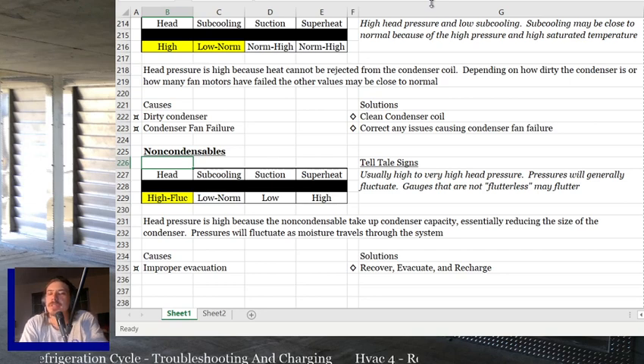But generally you're going to see head pressure start at 250, climb up to 300, 320, 350, drop back down, go back up, go back down, and it'll just keep fluctuating. The moisture traveling through the system freezing, or just the non-condensables moving in and out of the condenser essentially. The other thing you may see is super high head pressures. If you got nitrogen trapped in the condenser, basically it just takes up space in the top of the condenser.